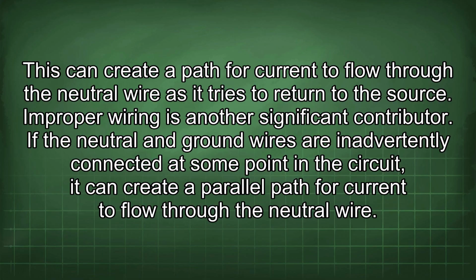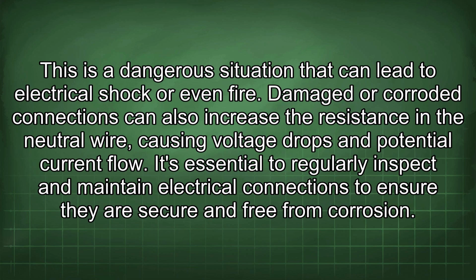Improper wiring is another significant contributor. If the neutral and ground wires are inadvertently connected at some point in the circuit, it can create a parallel path for current to flow through the neutral wire. This is a dangerous situation that can lead to electrical shock or even fire. Damaged or corroded connections can also increase the resistance in the neutral wire, causing voltage drops and potential current flow. It's essential to regularly inspect and maintain electrical connections to ensure they are secure and free from corrosion.